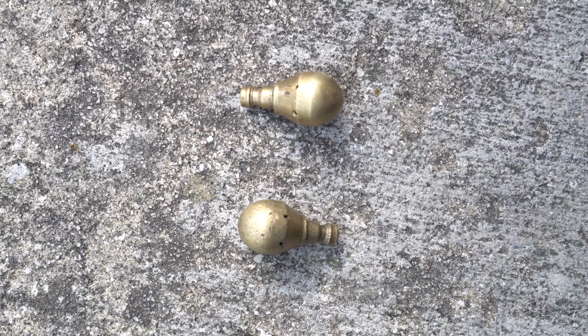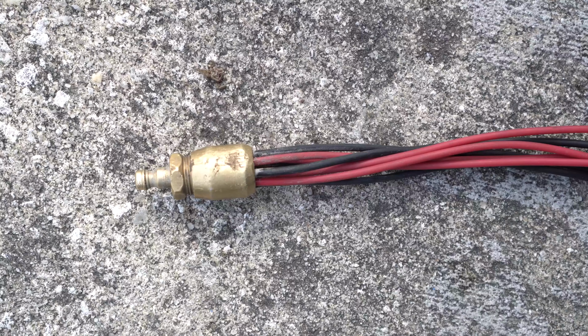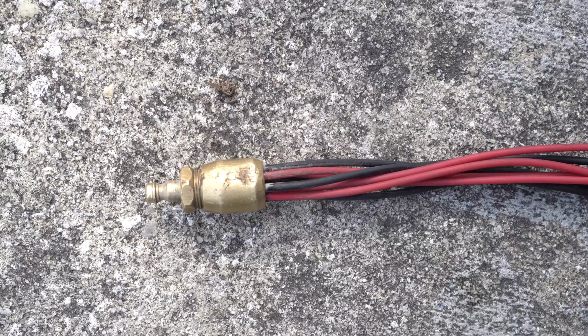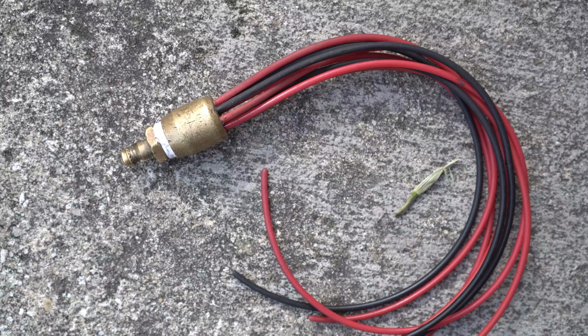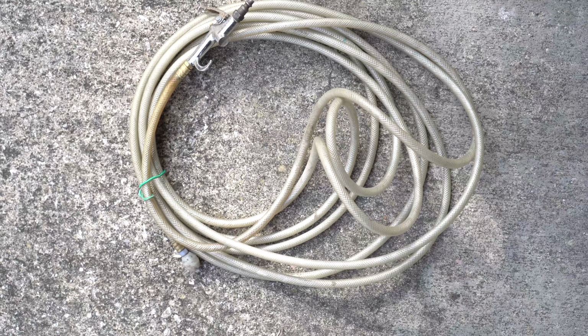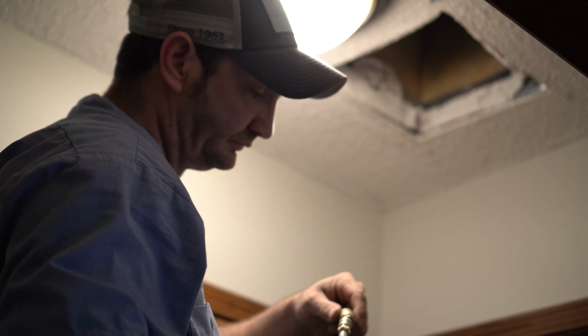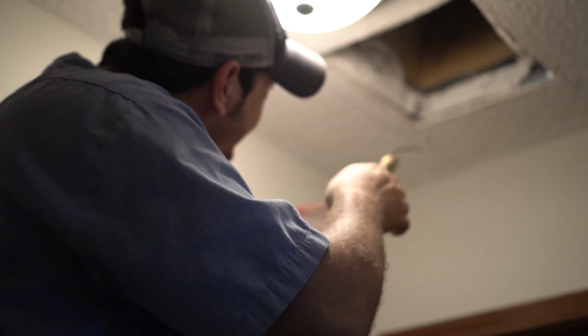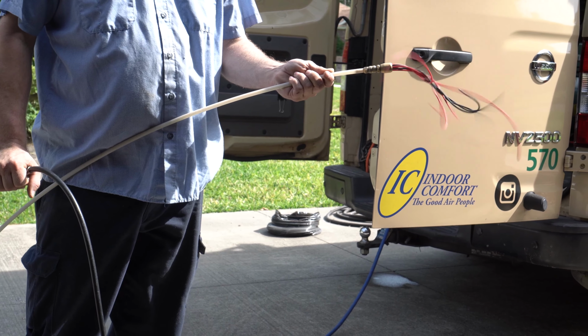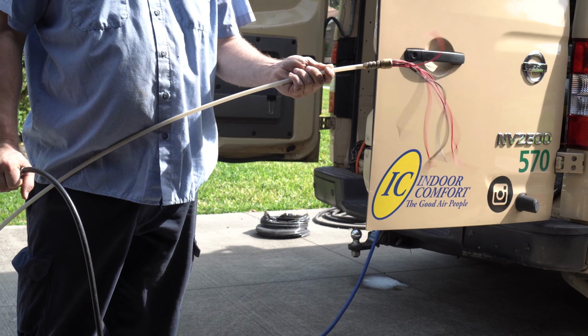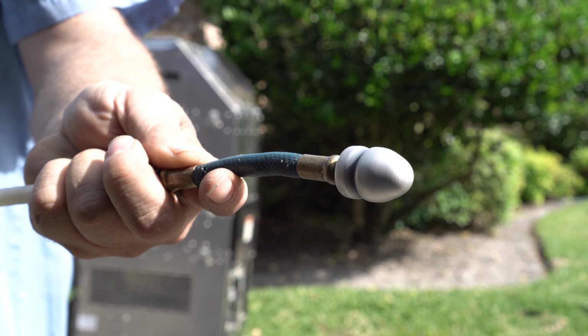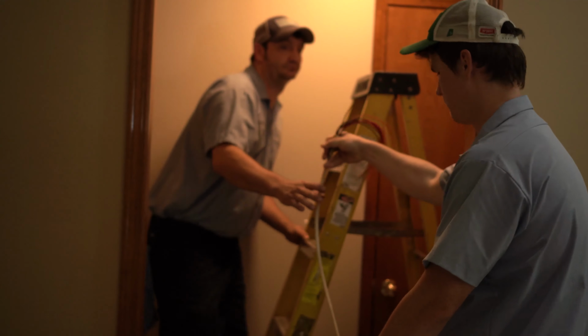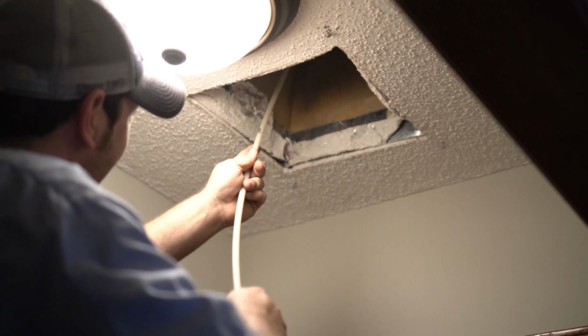Here are some of the most common tools used to perform duct cleaning operations. Forward and reverse nozzles. Whip heads that differ in length. The length you use will be determined by the duct diameter. Power rod system. This is a rigid rod system with quick connects that allow you to connect your tool to the end and feed it into the duct system. Forward and reverse air sweep assembly. This is a flexible hose with the air nozzle at the end and is great for limited access ducts or areas where you must reach the trunk through the interior boot.